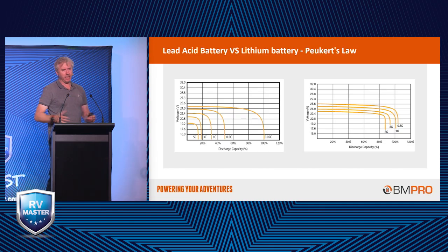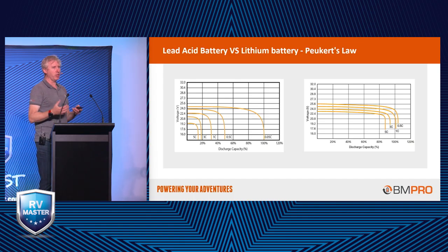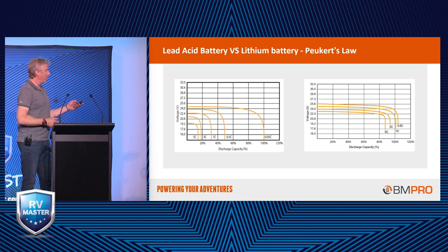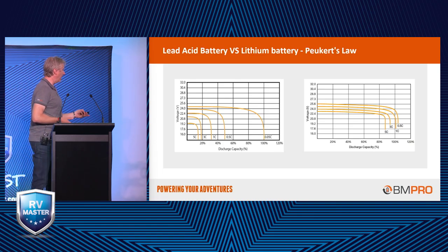Whereas on a lead acid battery, it's going to diminish very quickly. If you started pulling 100 amp hours out of a battery like that, you're probably going to see the capacity disappear in about 30 or 40%, three times faster than what you would normally see on a lithium battery. Basically you're going to flatten the battery a lot faster. So that's why you'd never use induction stoves, microwaves, or hair dryers. You can use inverters, but you'd want a large lead acid battery bank. If you're going to use a 2,000 or 3,000 watt inverter, you'd want at least 200 or 300 amp hours of lead acid batteries to do that. But the faster you take it out, the less you're going to have left in there.